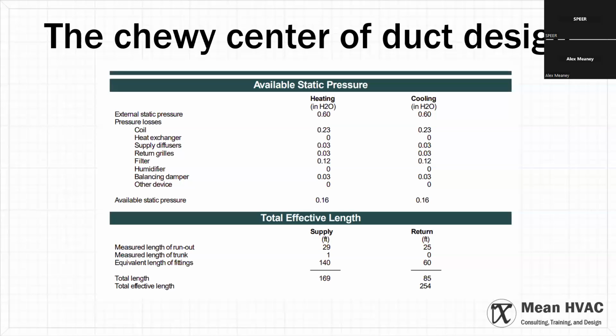Trying to verify and inspect every component of a duct system is madness. I've worked with inspection teams in certain municipalities on ways to move away from it because it just was slowing them down, and they switched to static pressure testing the unit once it was installed, putting the onus on the contractor. If it failed after the fact, they have to fix it, and it's more expensive to do that than to do it right in the first place. So that ended up being a pretty effective approach.